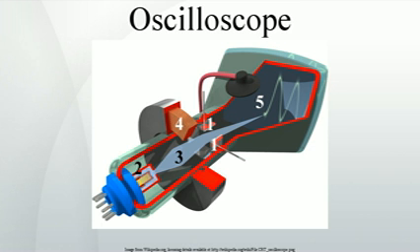Vertical position control. The vertical position control moves the whole displayed trace up and down. It is used to set the no-input trace exactly on the center line of the graticule, but also permits offsetting vertically by a limited amount. With direct coupling, adjustment of this control can compensate for a limited DC component of an input.